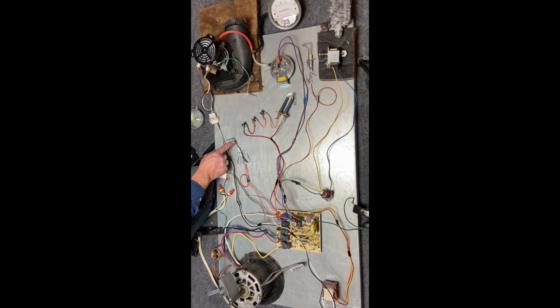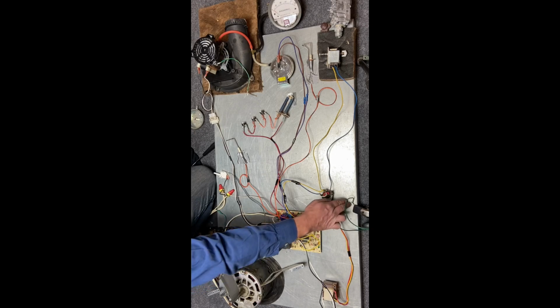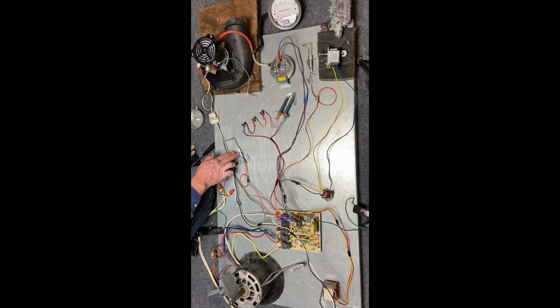This wire is going to our flame sensor. So the flame sensor proves a flame through a process called flame rectification. The flames actually convert this from an AC current to a pulsating DC current, and the control board reads that through the ground wire. And here we have our ground wire connected to this board, and there's also a green ground wire here connecting it to our board. So that has only one wire.